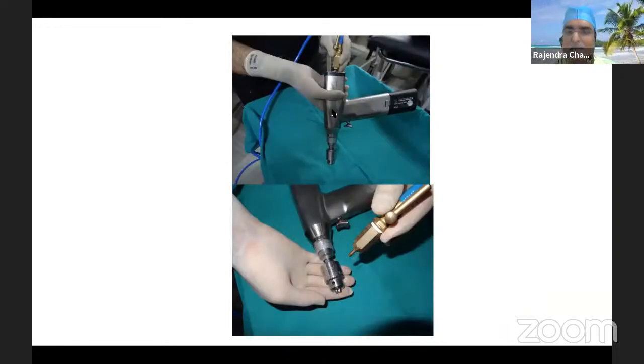And the cleaning and maintenance of a drill also requires certain inputs. A very easy way is the dental surgeon's air pressurizing machine, which cleans the drill and drives out all the water through it so that your sterilization is perfect. Never ever dip all these chucks into saline water, and that's a very important thing. When you dip the chucks into saline or an NaCl solution, the sodium crystallizes, and this crystallization leads to jamming of the chuck, and that leads to a problem. So pour running water, or you can use the simple autoclave water, whatever you want to use, but avoid using saline for this function.